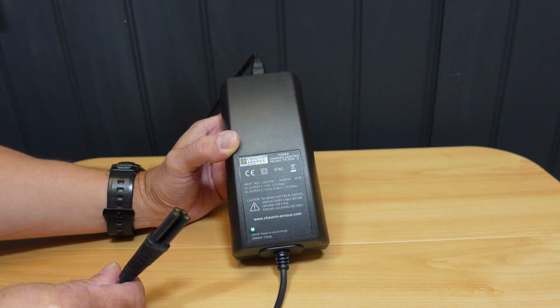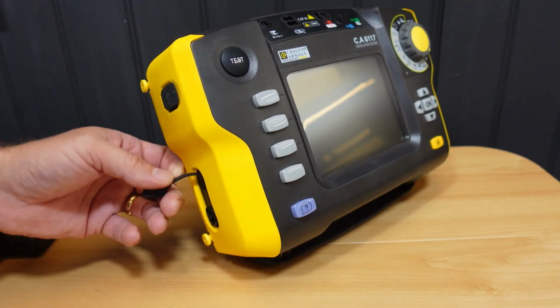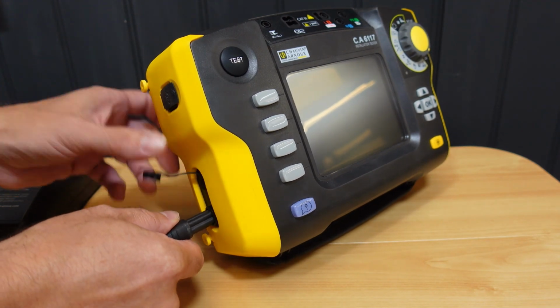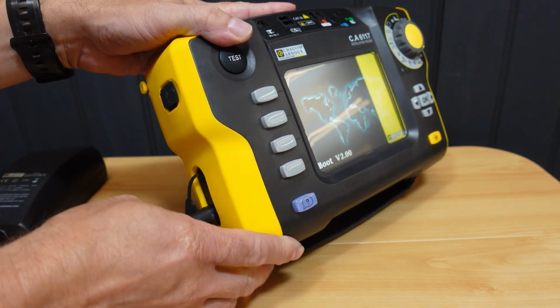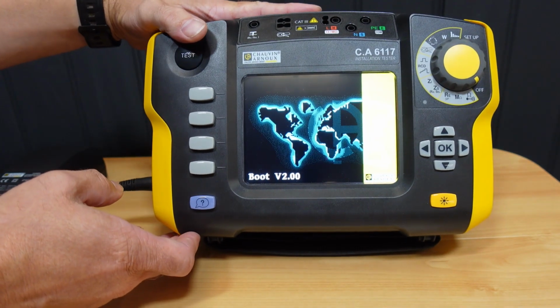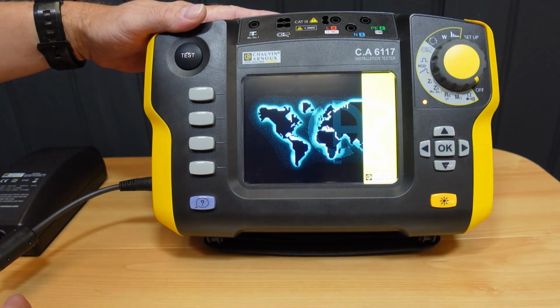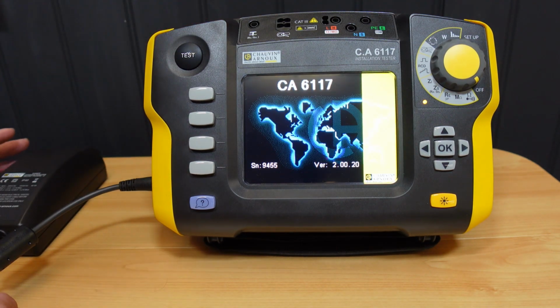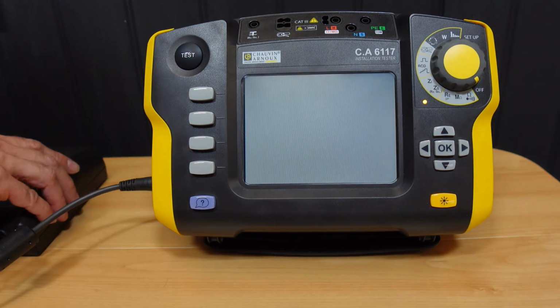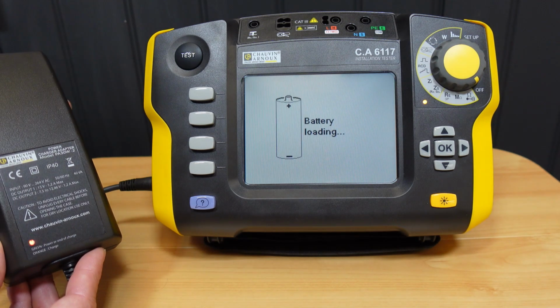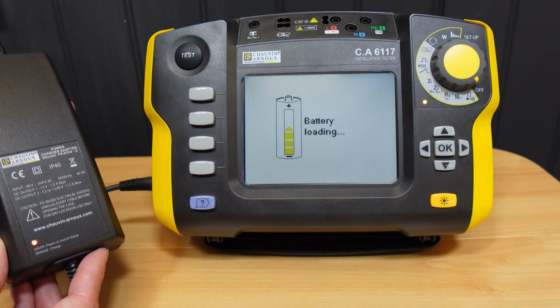Charging requires the use of the Chauvin PA30W power supply. This connects to the power port on the left side of the 6117. An orange indicator on the power supply and a battery loading screen on the tester will confirm charging is underway. The instrument cannot be used for capturing results whilst in charging mode, although we can familiarise ourselves with basic operation and initial setup while it is plugged in.